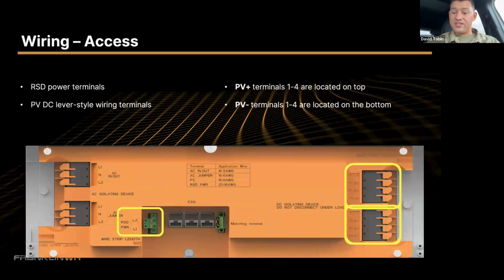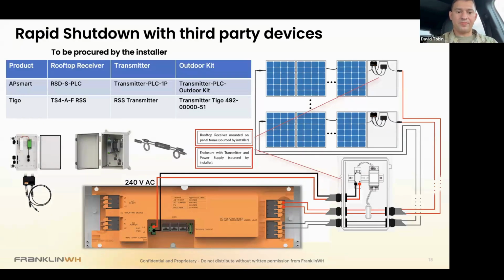And then for the DC side, you can see we have 4 strings, PV positive, PV negative. We also have a location to wire up AC power to your rapid shutdown transmitter. So you will still require a power supply that would allow the conversion of 120 to 240 volt AC into the 12 or 24 volts for the transmitter. These are the two products that we are compatible with for rapid shutdown, AP Smart and Tigo.